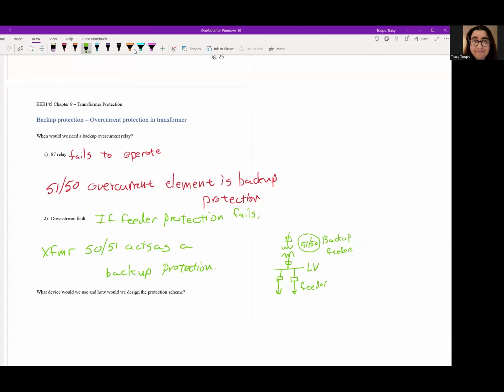So it's dual function. This overcurrent protection for the transformer protects the transformer itself. It also helps the other feeders and substations as a bonus. Okay, because remember, with protection elements and devices, we make a holistic system where every device will cover at least some other device, to where if we look at the substation as a whole, we should have maybe 15 devices, all crossing over each other's zones just to give overlapping zones of protection with primary and backup systems. Okay. So what device would we use, and how do we design a protection scheme?